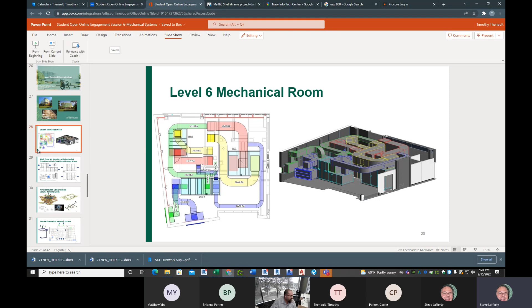So the other part of this dedicated outside air system is the green exhaust that we're showing. It comes up through the shaft right here from the toilets and whatnot, and comes through the dedicated outside air system and blows out to the outside. We're also pulling air that would normally be returned for exhaust through the system to blow it to the outside. And as we've looked at in the previous building, this unit has a wheel right here that spins. So as this cold air goes through the wheel and spins it, it cools down this section of the wheel.